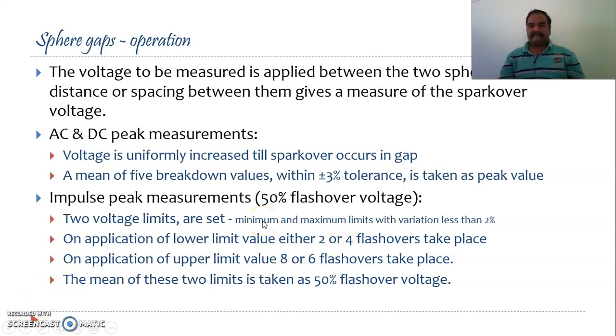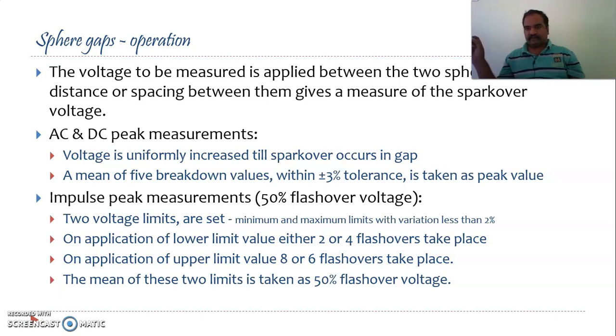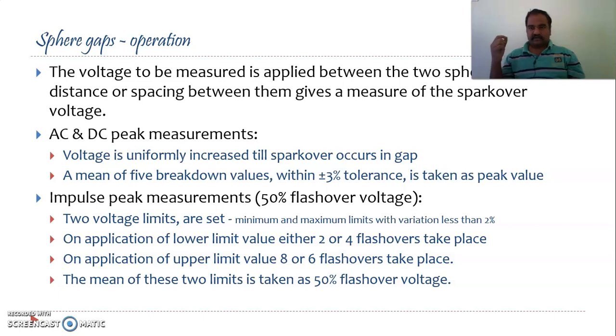For AC and DC signals, voltage is uniformly increased until spark-over occurs in the gap, and this process is repeated — voltage is slowly increased until the spark-over happens. This process is to be repeated 5 consecutive times to ensure you have an accurate value. If the values obtained across all 5 readings are close enough — within ±3% tolerance — then it is considered the final value and declared as the peak value of the given signal.